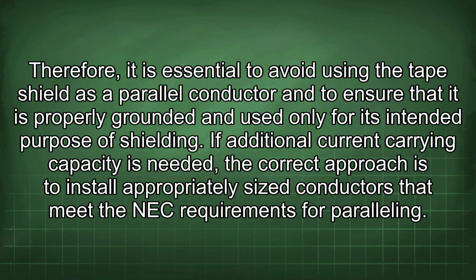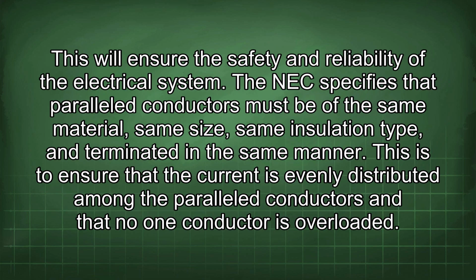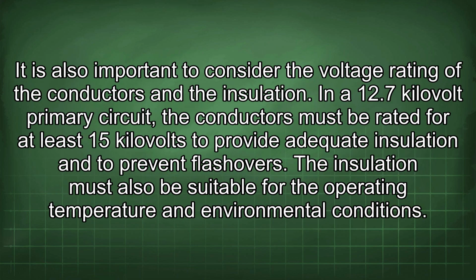If additional current carrying capacity is needed, the correct approach is to install appropriately sized conductors that meet the NEC requirements for paralleling. This will ensure the safety and reliability of the electrical system. The NEC specifies that paralleled conductors must be of the same material, same size, same insulation type, and terminated in the same manner. This is to ensure that the current is evenly distributed among the paralleled conductors and that no one conductor is overloaded. It is also important to consider the voltage rating of the conductors and the insulation. In a 12.7 kilovolt primary circuit, the conductors must be rated for at least 15 kilovolts to provide adequate insulation and to prevent flashovers.